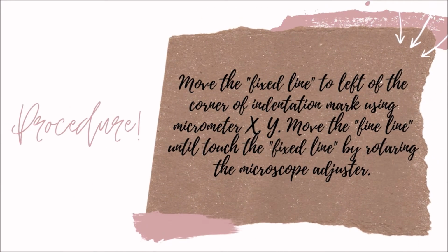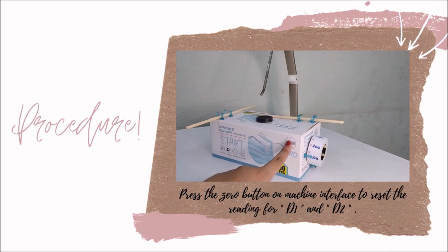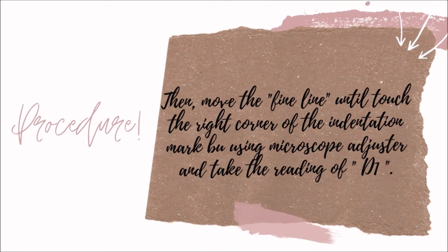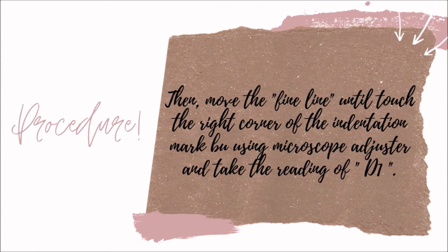Move the fixed line to the left corner of the indentation mark using the micrometer X, Y. Move the fine line until it touches the fixed line by rotating the microscope adjuster. Press the 0 button on the machine interface to reset the readings for D1 and D2.